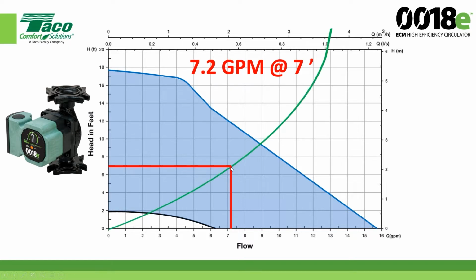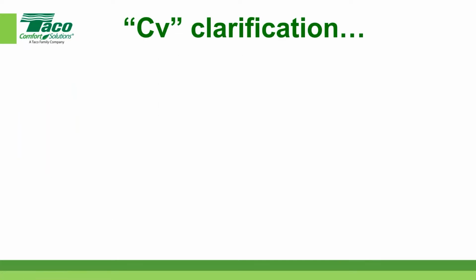My duty point would be where it's going to operate at something less than maximum speed. When we talk about something at maximum speed, we call that the operating point. My duty point's down here. Duty means what does it need to do under that design condition that is specific to that job. Hopefully that helps out. So that would be the duty point, or the operating point if it slid all the way up here. This thing here is our system curve, and we're going to talk about that in the next segment.